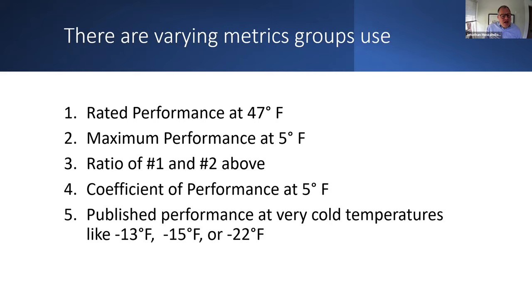Now, finally, and this is something both of our brand standards conform to, is publishing rated performance of heat output at very cold temperatures. Each brand's a little different. Sean and I both work at companies that will mostly use negative 13 as our published performance floor. But some of our models, at Daikin, we produce down to negative 15. One of our competitors produces down to negative 22. When you're really cold, in climate zones 6 and 7, those numbers become really important for heating contractors too. I'll add to that too. It depends on the model.